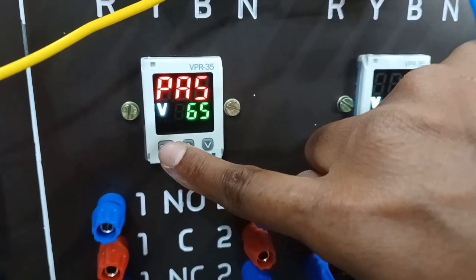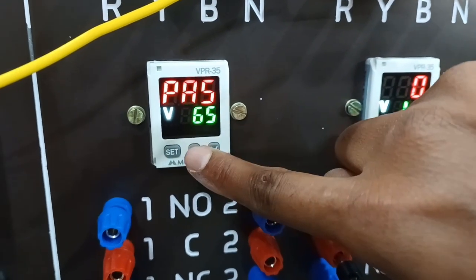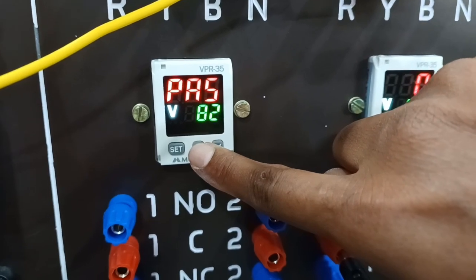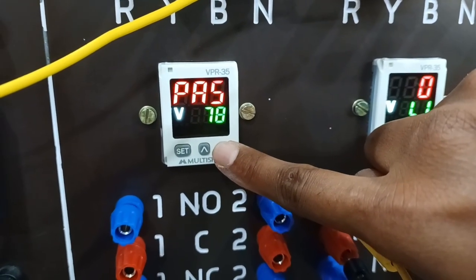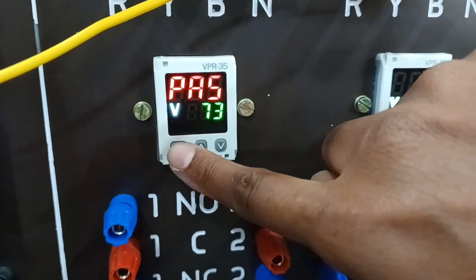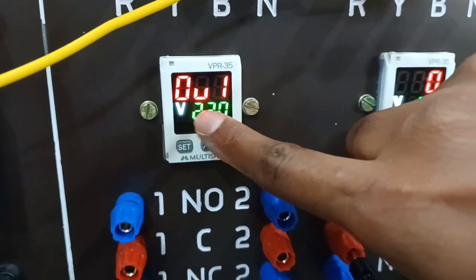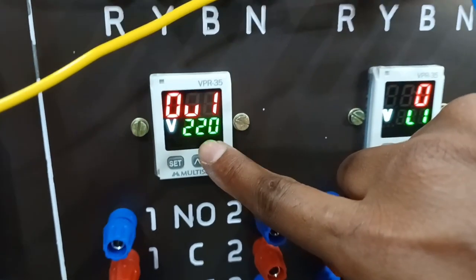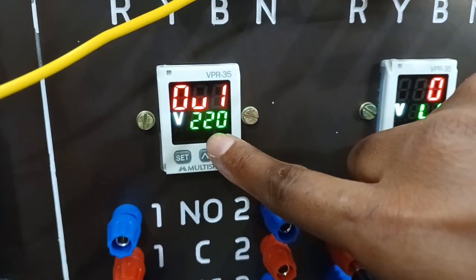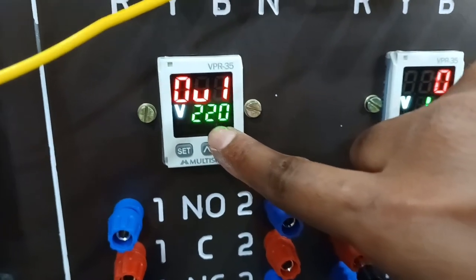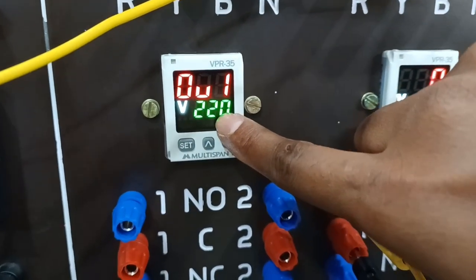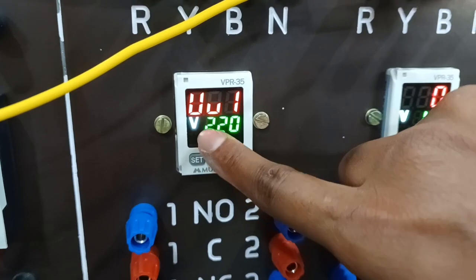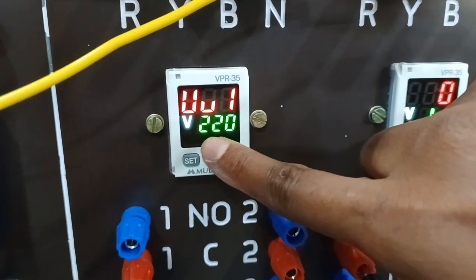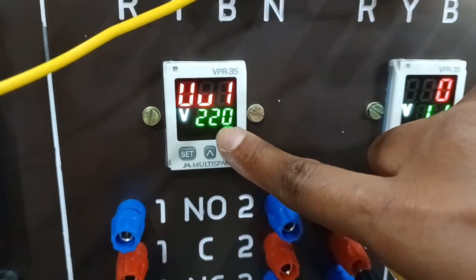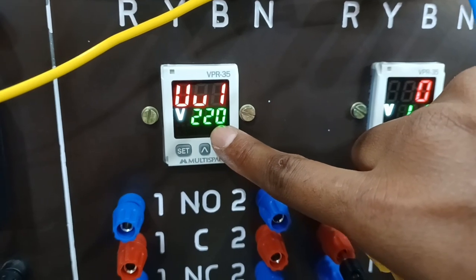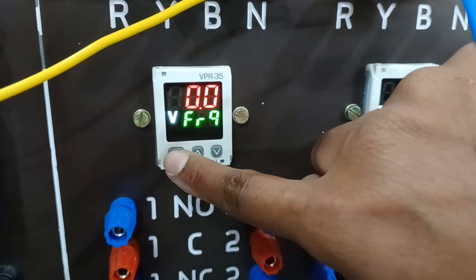And coming to fault settings, percentages, the password will be 78. Now you can look at the over voltage value, which is 220 volts. Whenever the voltage is above 220, it will be treated as an over voltage fault. Similarly, the under voltage fault is also 220; whatever the voltage is less than 220 will be treated as an under voltage fault. This is the programming.